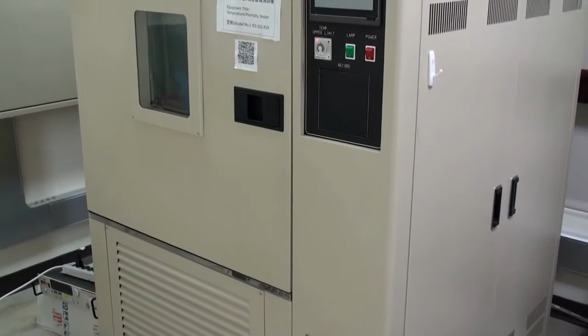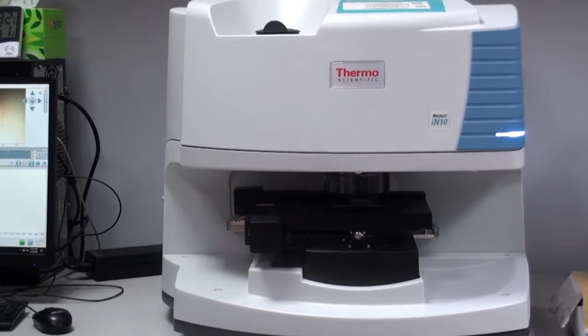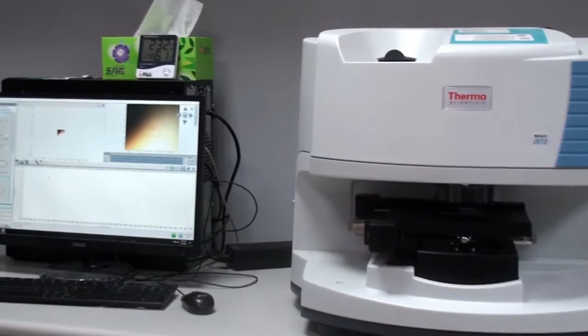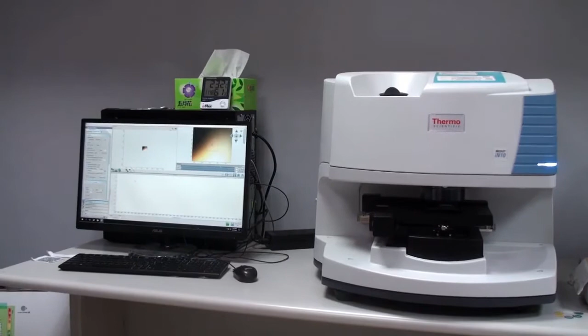This is a Fourier transform infrared microscope from Thermoscientific, model number IN10 Nicolet. It is used for microspectroscopy and material identification. It has two modes, room temperature and cool mode, for higher accuracy, with basic and advanced data processing program customization. It is incorporated with Thermoscientific Omnic Picta software for reliable results, and the Nicolet IN10MX microscope for better speed and sensitivity of single point measurement and good quality chemical imaging.